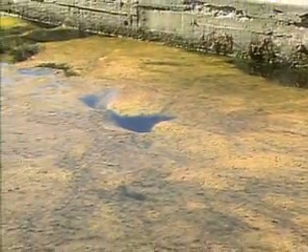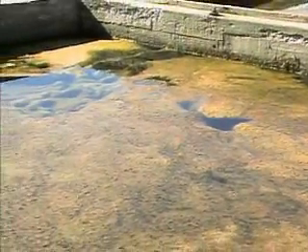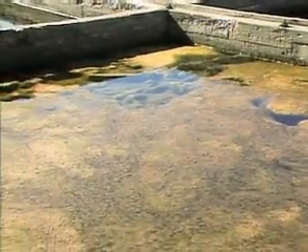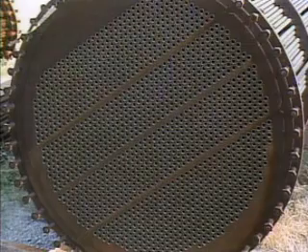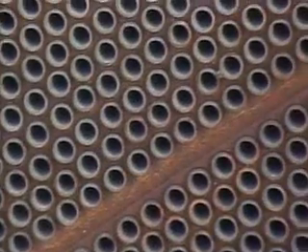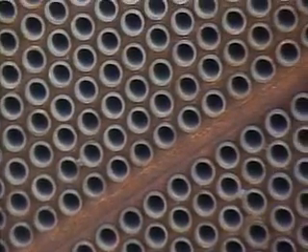Microorganisms are very small plants and animals, such as algae and bacteria. Air and sunlight stimulate microorganism growth, so cooling towers make good breeding grounds. Microorganisms often create thick, gummy slime growths that can foul tubes and heat exchangers and reduce the amount of heat that can be transferred. Another problem with microorganisms is that they can release gases such as oxygen inside cooling systems. This can promote corrosion of the equipment in the system.